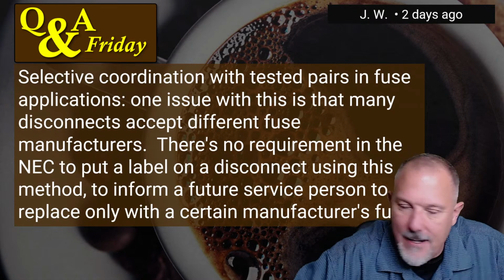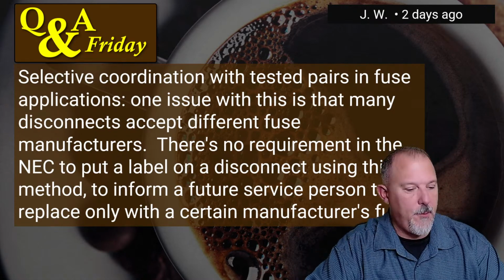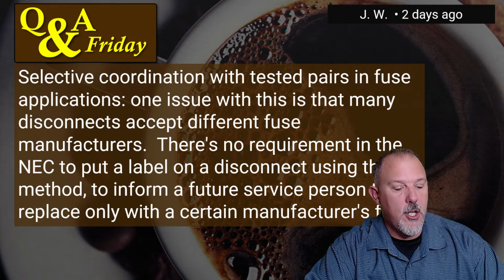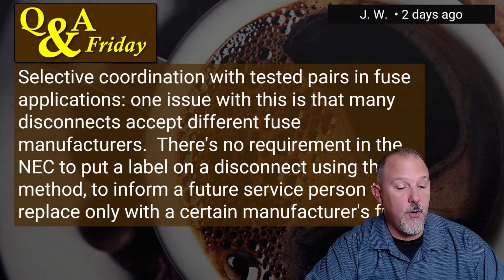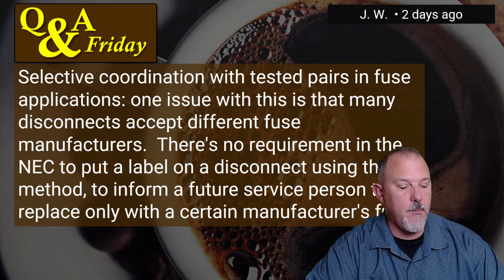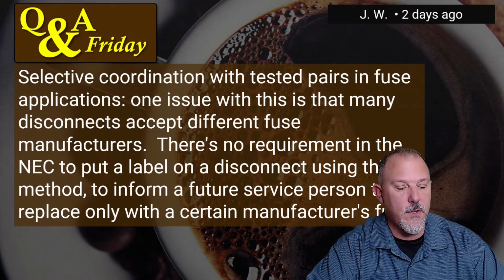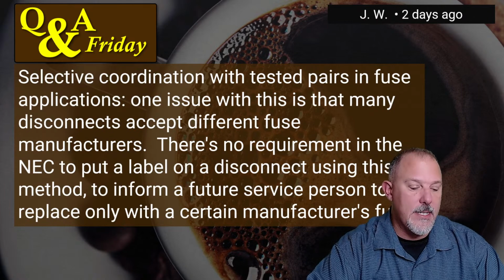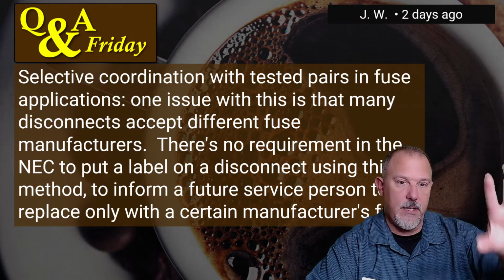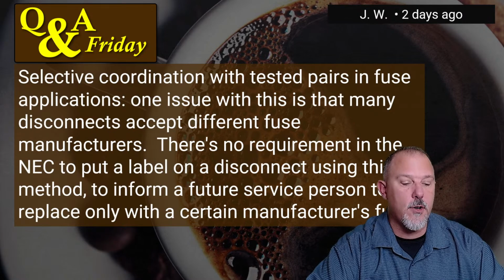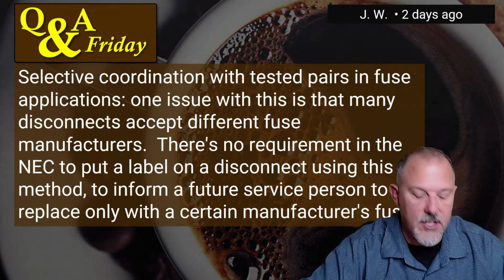All right. JW, I'm glad we revisited this question. Equipment enclosures containing selectively coordinated overcurrent devices shall be legibly marked in the field to indicate that the overcurrent devices are selectively coordinated. The marking shall meet the requirements of 110.21(B) and it gives us exact language: Caution, overcurrent devices in this enclosure are selectively coordinated. Equivalent replacements and trip settings are required.